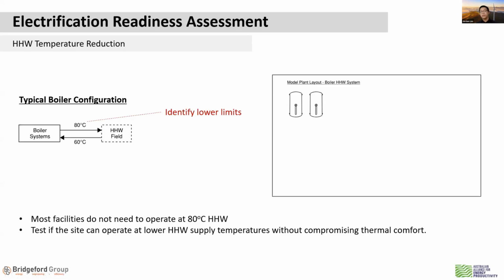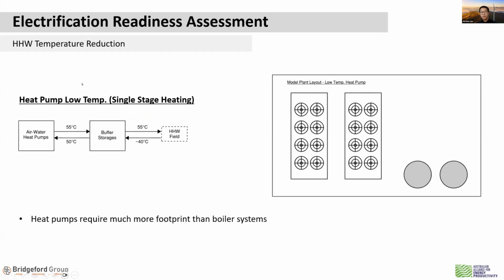a gas-fired boiler system. If we move on to the next slide, if you can identify that your heating hot water plant can operate at a lower temperature, say 55 degrees, rather than 80 degrees, you'll be able to design for a heat pump system that allows what we call single stage heating, relying on just air source heat pumps to supply lower temperature heating hot water, say 55 degrees, to deliver heating. The picture on the right now shows a heating hot water plant with a much higher footprint requirement than the gas-fired boiler plant shown earlier. This is something asset owners need to be aware of when deciding on electrification, because while it's efficient and helps decarbonize the building, it does take up a lot of real estate. It's not uncommon to see up to 10 to 15 times the footprint requirement of a gas boiler system for an air source heat pump heating system.